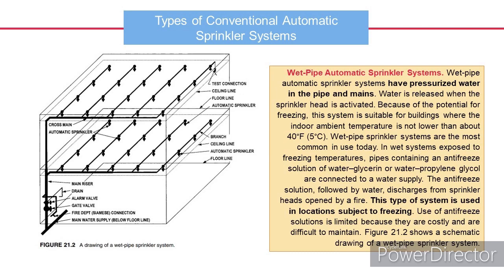In wet systems exposed to freezing temperatures, pipes containing an antifreeze solution of water and glycerin, or water and propylene glycol, are connected to a water supply. The antifreeze solution, followed by water, discharges from sprinkler heads opened by a fire. This type of system is used in locations subject to freezing. Use of antifreeze solutions is limited because they are costly and are difficult to maintain. Figure 21.2 shows a schematic drawing of a wet pipe sprinkler system.